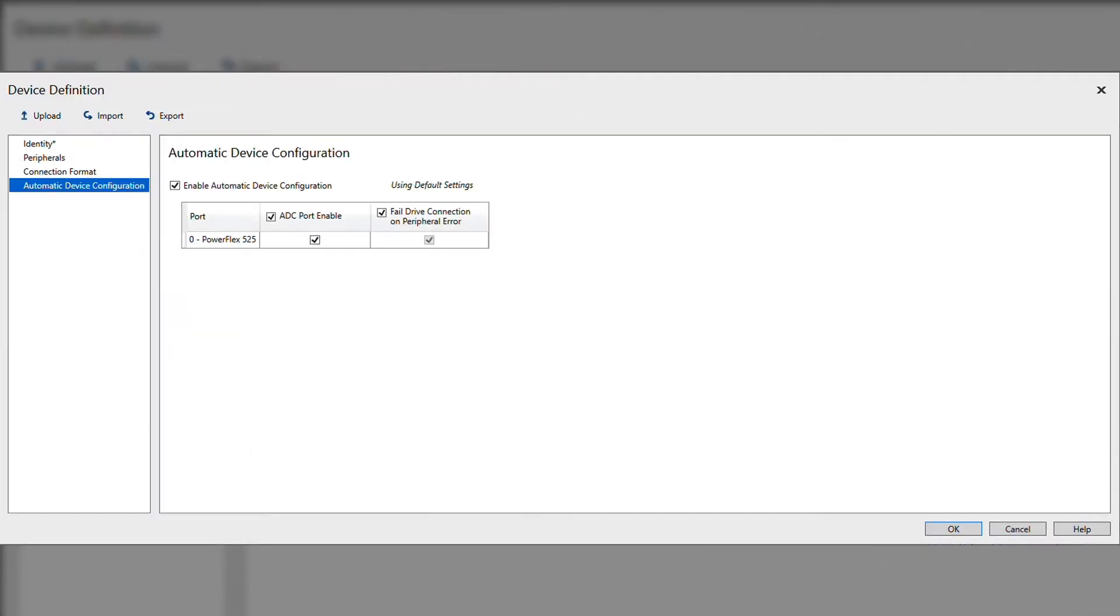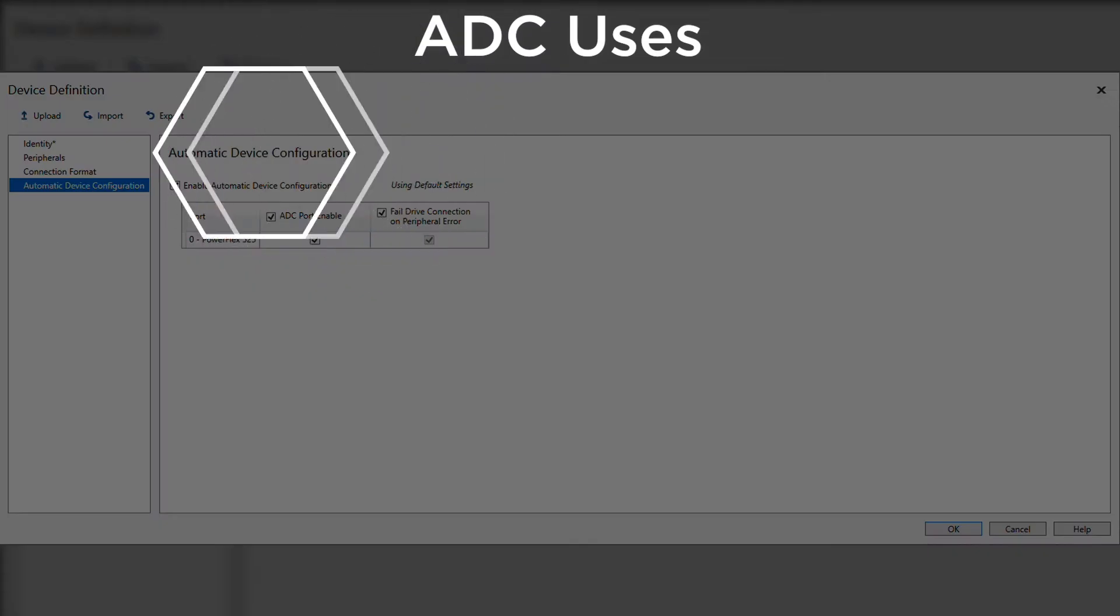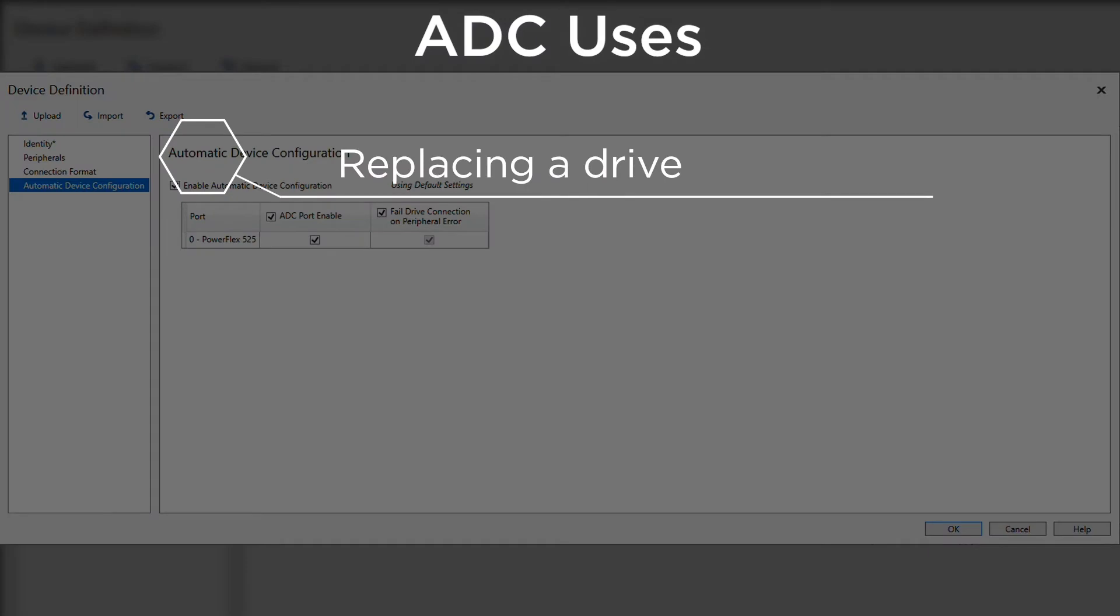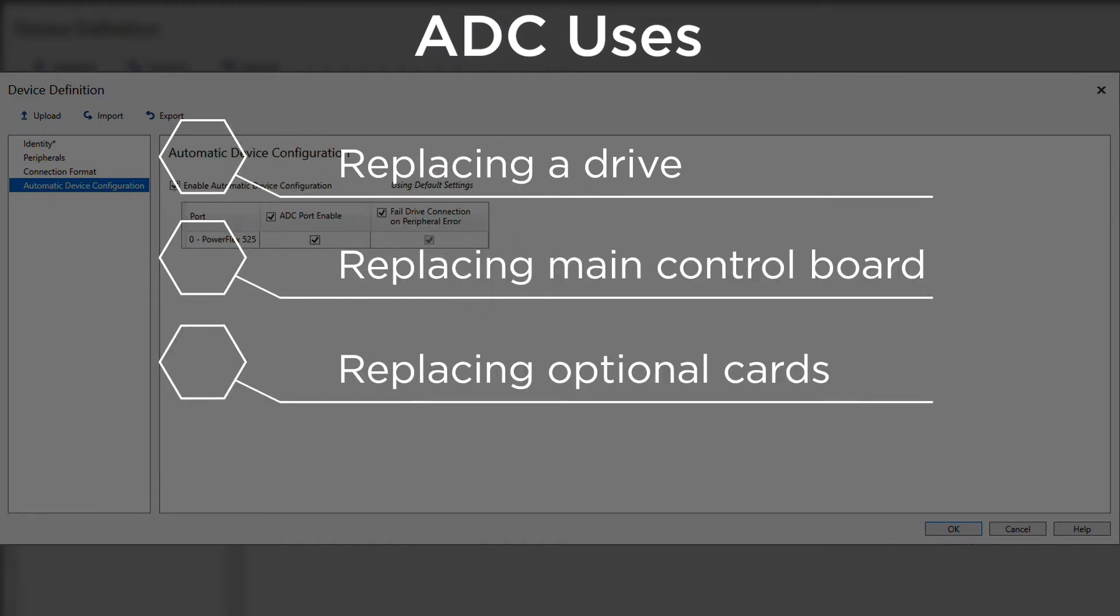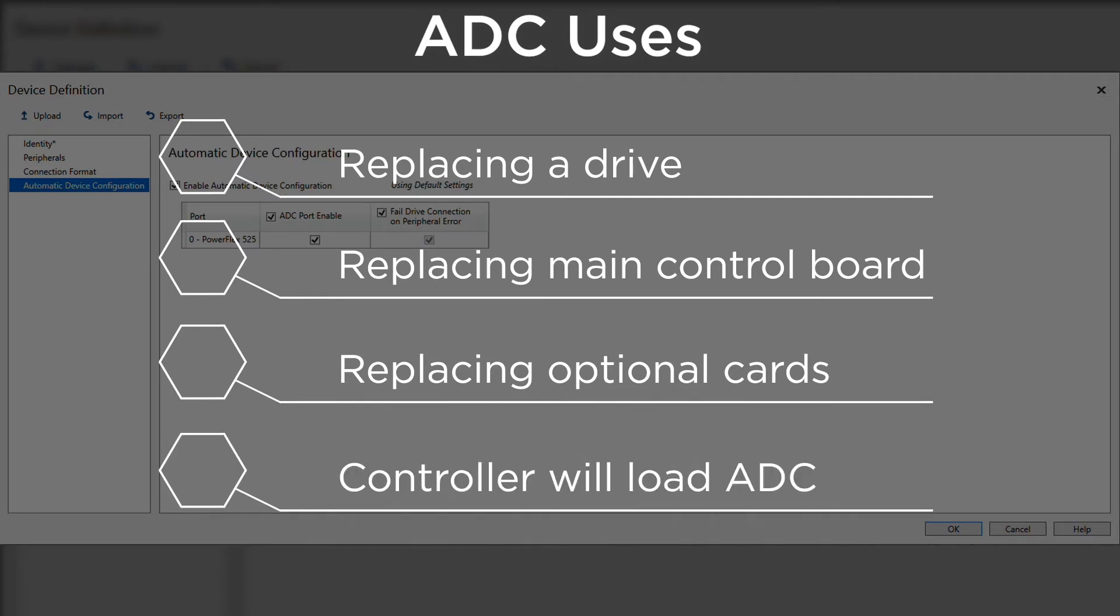ADC is primarily used when replacing a drive, the main control board, or the optional cards. The controller will automatically load the saved configuration into the new module without the need of manually downloading the parameters into the new drive.